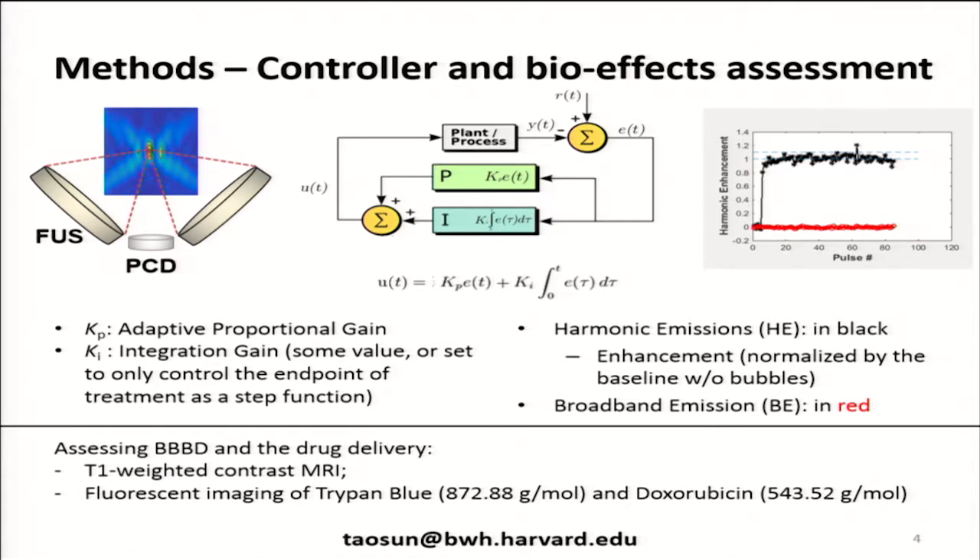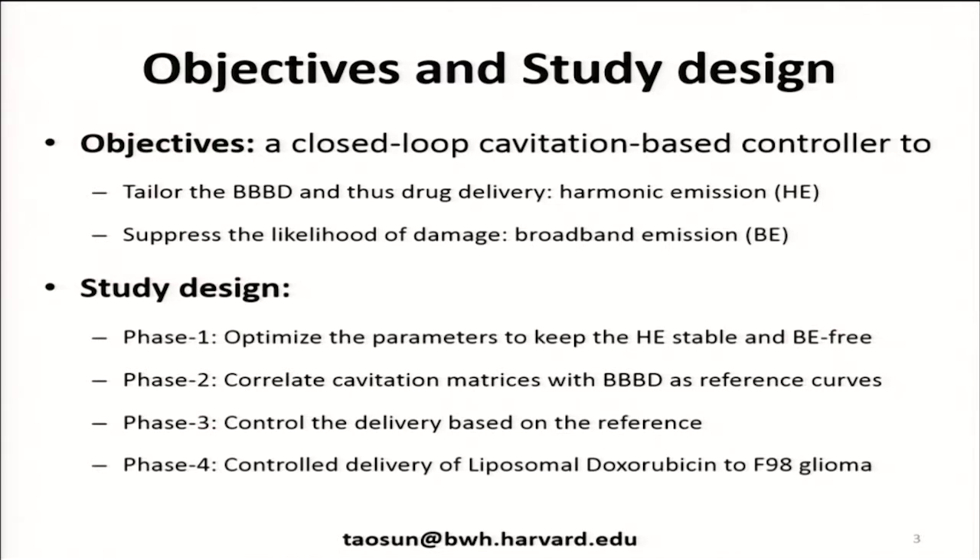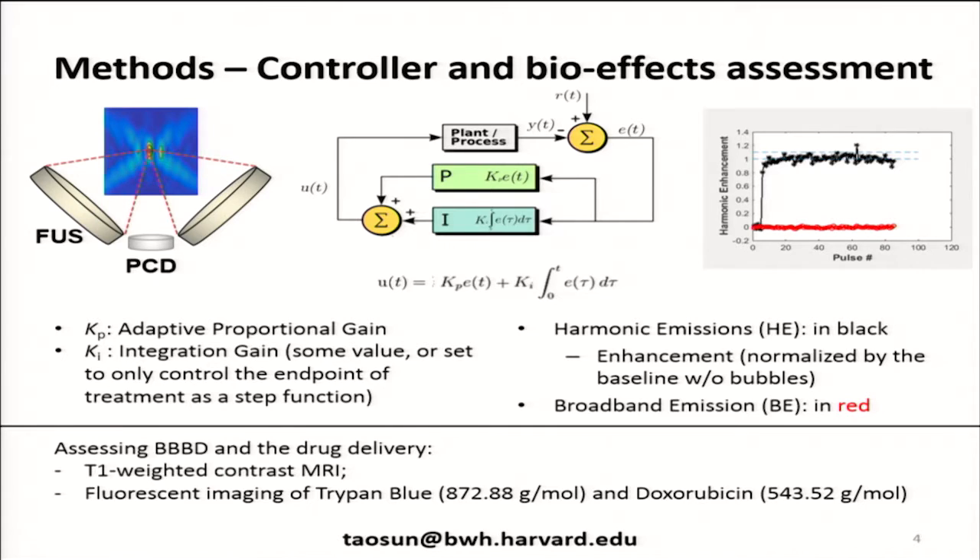The system we built is a two-transducer system that operates at a frequency similar to what we'll be using with the Exablate Neuro — this one operates at 270 kilohertz. To reduce the size of the effective focal area, we use two transducers with an overlapping focus, and the actual focal spot of BBB opening is smaller than the rat brain, typically covering its entire thickness. It also gives us a nice area to place a passive cavitation detector. We built a proportional controller that actively controls power level to maintain a prescribed level of harmonic emission, and if we see any broadband emission, it either stops the sonication or reduces the power. We used MRI and fluorescence imaging of trypan blue and doxorubicin to validate this controller.